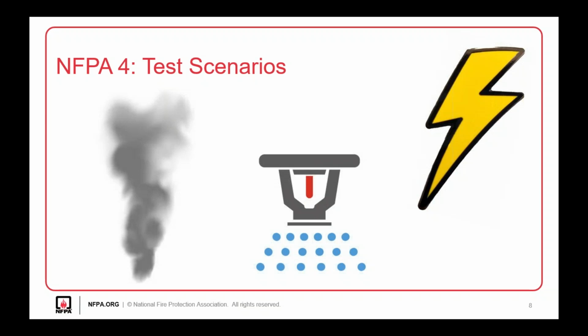When you look at one or a combination of these events, there are obviously buildings out there that may not fall within one of these scenarios that would really test the building. You really want a test scenario with teeth, because you want to stress these systems. I look at these three events, one or a combination, as an 80-20 view, meaning for a majority of buildings in the world, if one of these scenarios occurs, you're going to start to see the domino effect of your systems communicating with one another, or see that they're not communicating with one another.